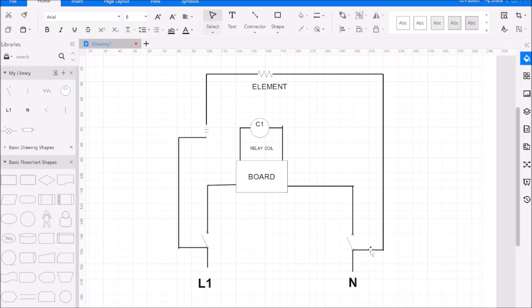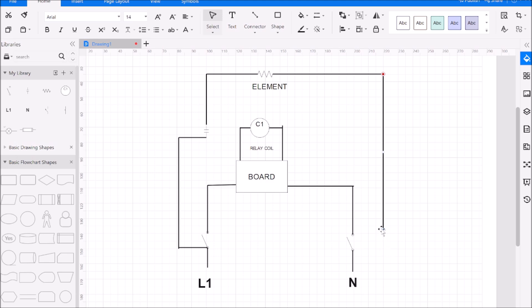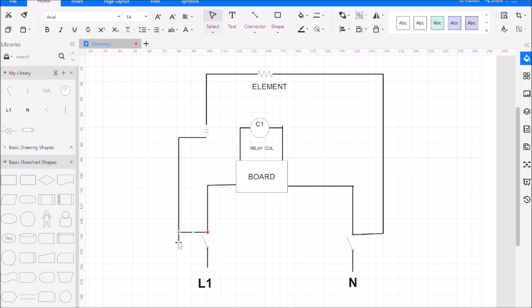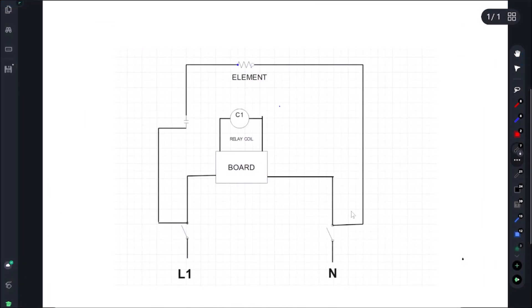Alright, so now the last thing I want to do is just go over why that happened. So this is how the unit should have been wired. Our neutral should have came in and it should have been connected on the outlet of this power switch. It was connected on the incoming of the power switch, and then I would have done the same thing on the L1 side. I would have brought this wire up and moved it over here. With it wired that way, let's go see.